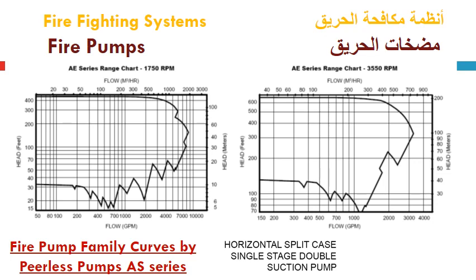This slide compares two family curves for Peerless pumps, AE series of horizontal split case single stage double suction pump. The left hand side shows the AE series range chart at 1750 RPM when using two pair of pole motor at 60 Hz. The curves are given in both units, SI units and British system units, with the head or the pressure in feet in this direction and in meter in this direction, and the flow in GPM at the bottom and the flow in meter cube per hour on the top.